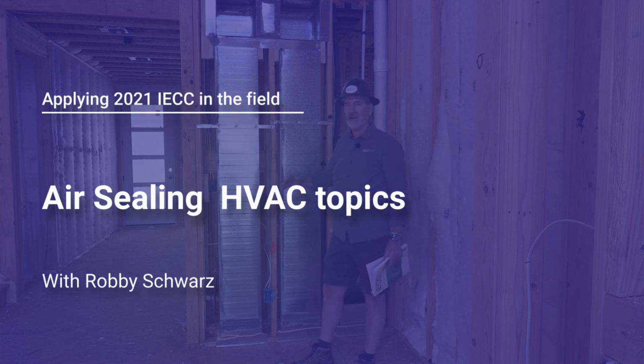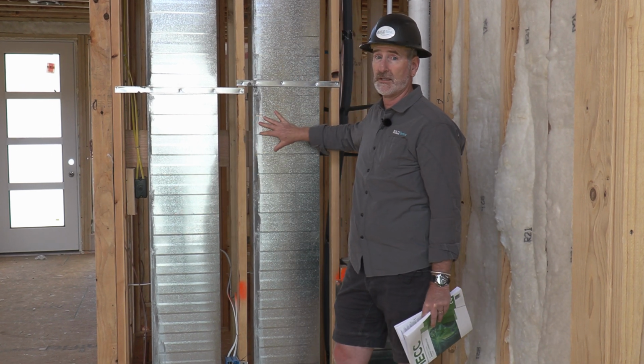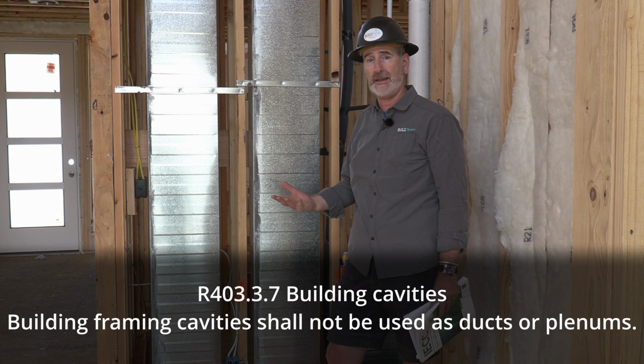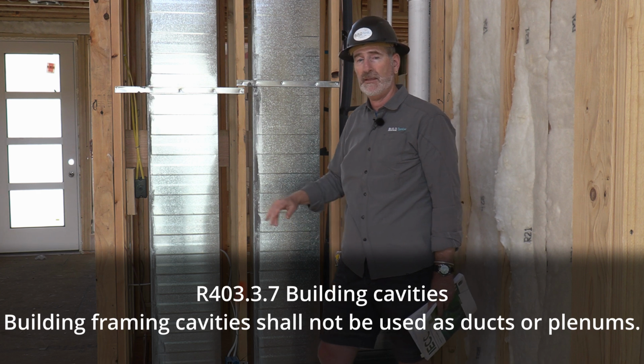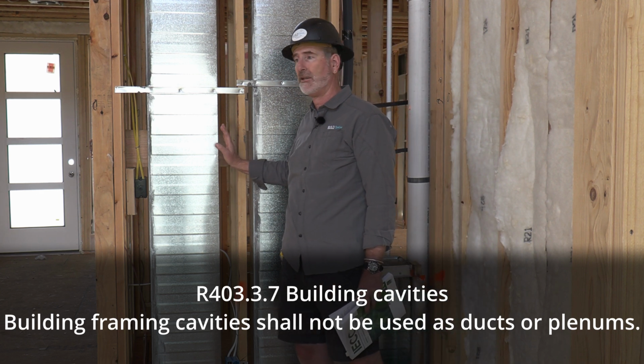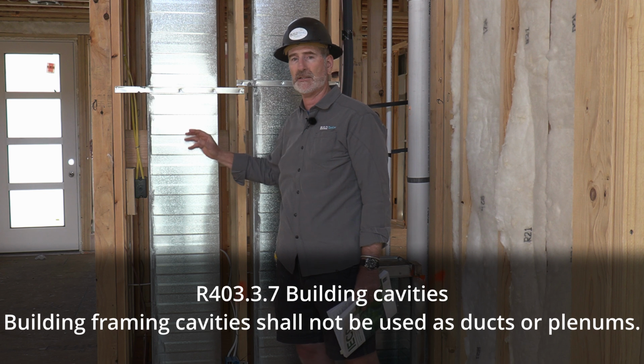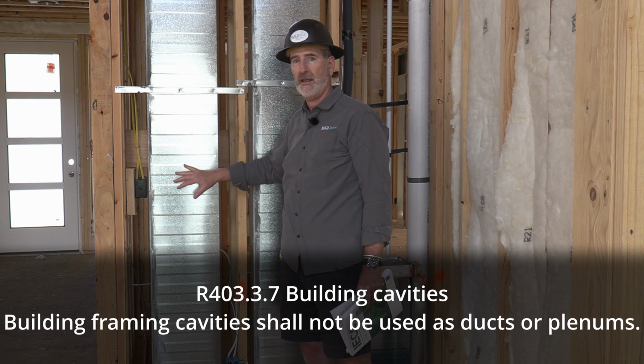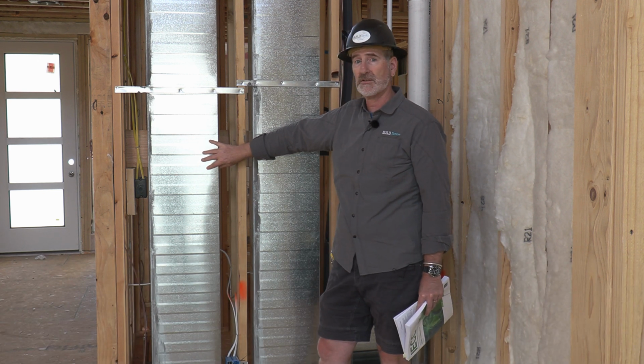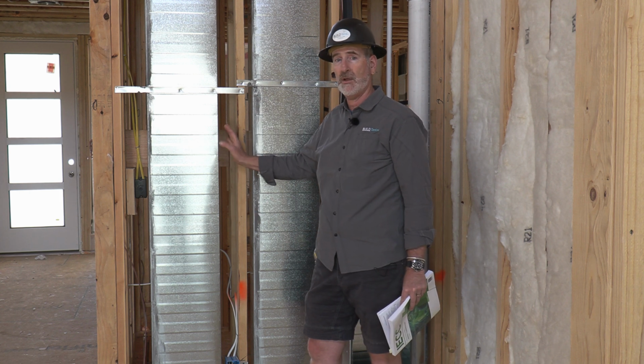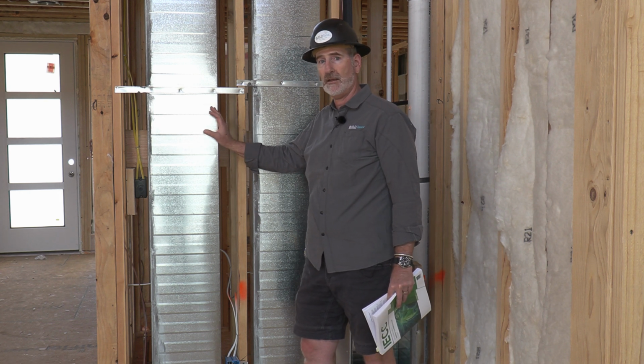I'm walking around the house with my code book and I'm trying to understand, how do I deal with ducts that are inside a building cavity? In this case, we have a return system here, and it specifically says in the R403 section, the mechanical section of the energy code, that you can't use building cavities as pressurized duct systems. Therefore, the way that they installed this return system with a ducted system here is compliant with the code.